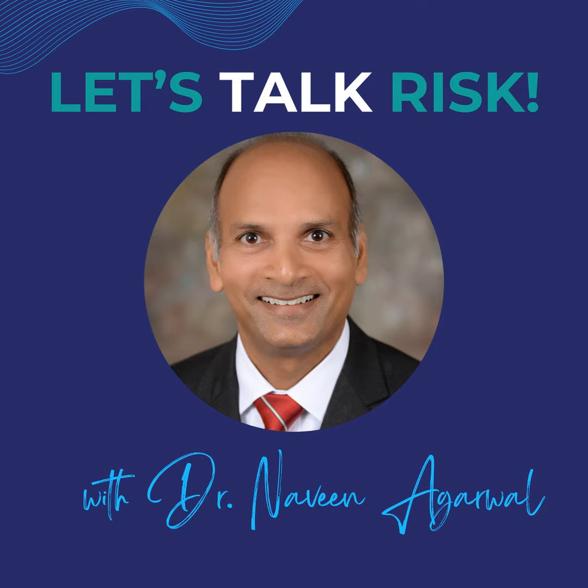They do the FMEAs, like system design FMEAs, URRA, cybersecurity FMEA, software FMEA, process FMEA. So one way to connect to the top-level hazard analysis from ISO 14971 is that those FMEAs are limited to a standard end effect at the system level, and those end effects are connected to the hazardous situations that predict P1.